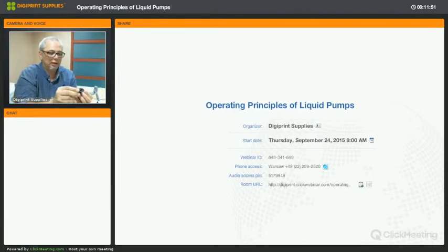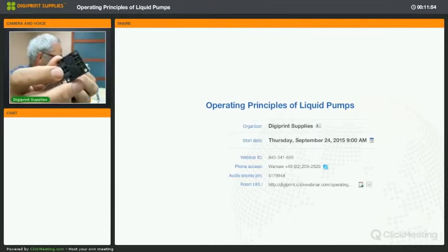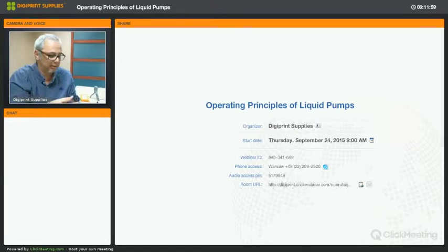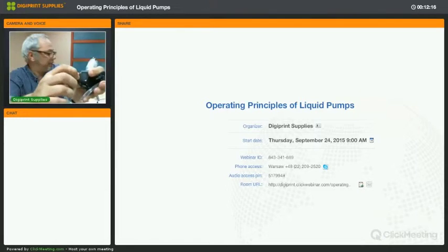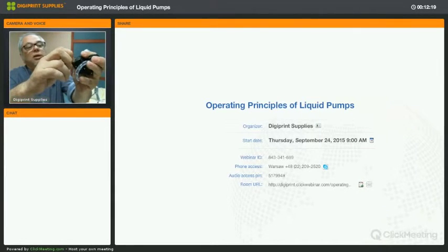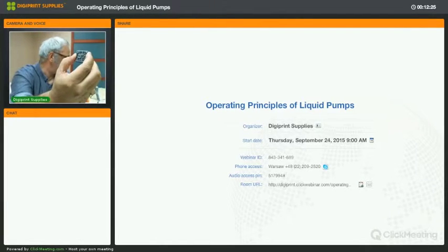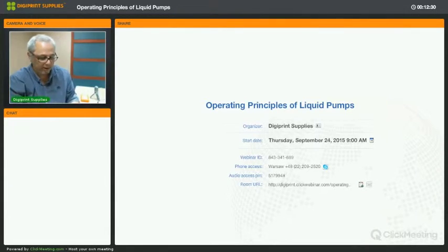Right. So see, this is how it looks on the inside, and if you look closely, you can already see 2 seals there. Take this out. A little bit of liquid is still inside. Can you hand me a bit of paper towel? Yeah, thank you. So here you can see the membrane. That's the thing that opens and closes the in and outlet. And actually, what you see here, the 2 circular parts, are the in and outlet valves. So that's how it looks on the inside.